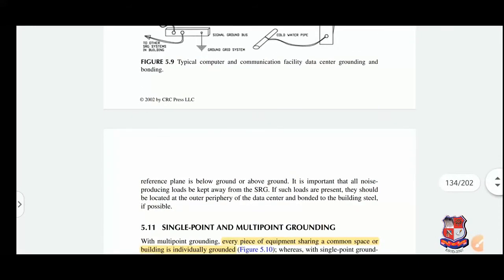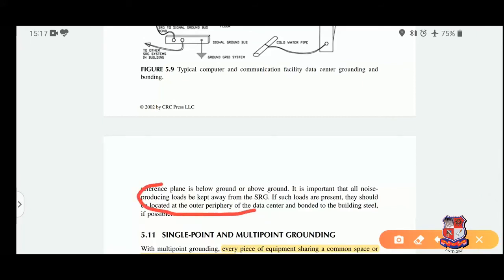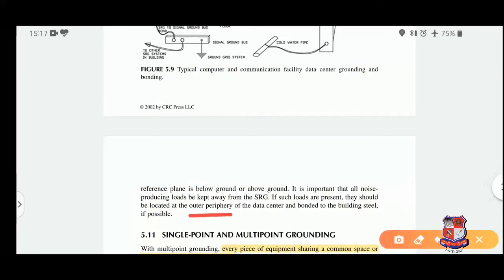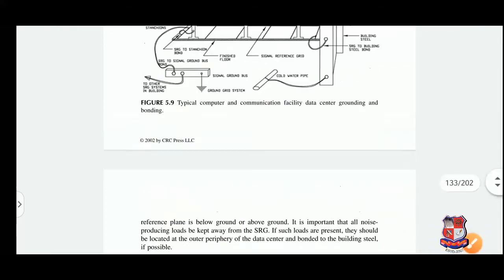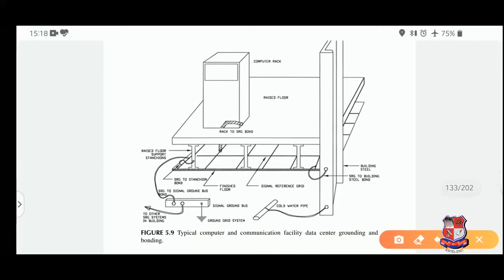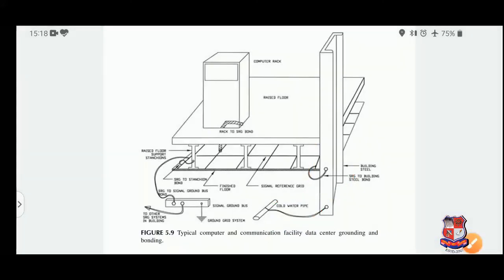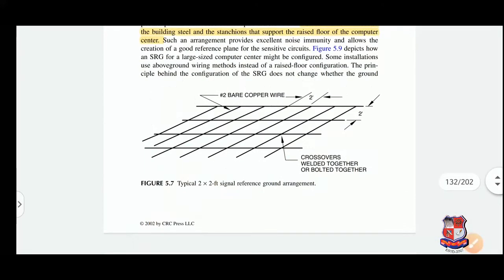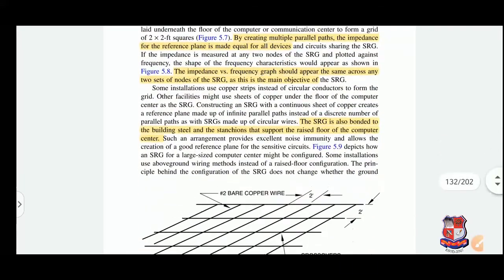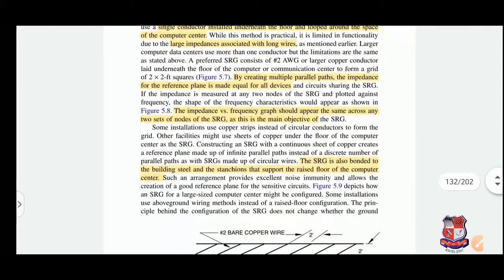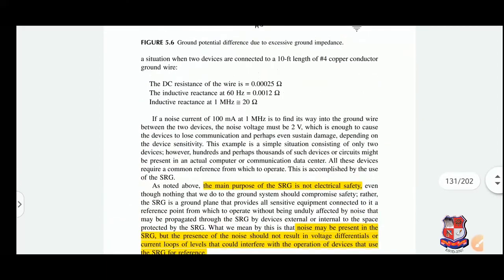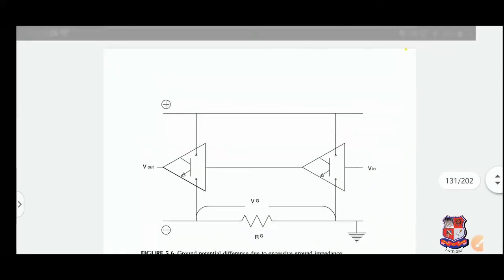One important precaution: all noise-producing loads must be kept away from the SRG. If such loads are present, they should be located at the outer periphery of the data center and bonded to the building steel, so that they can easily create a low-impedance path to ground. In this way, we can understand the signal reference ground method — how it is constructed, what its purpose is, and how it is useful for sensitive equipment. Thank you very much.